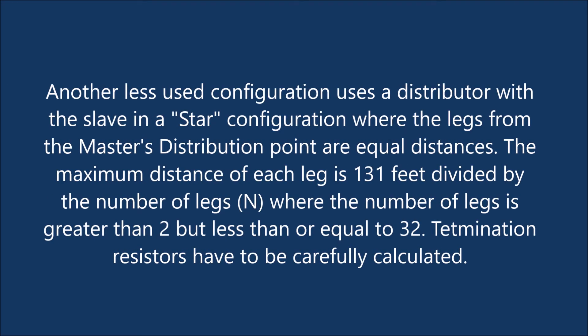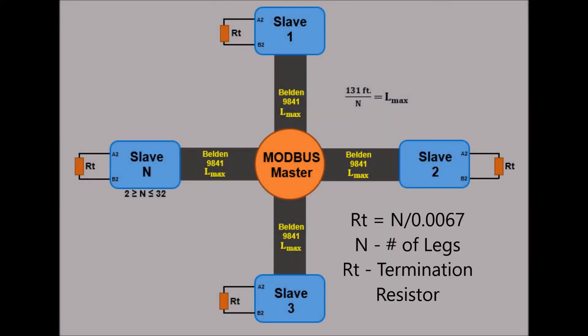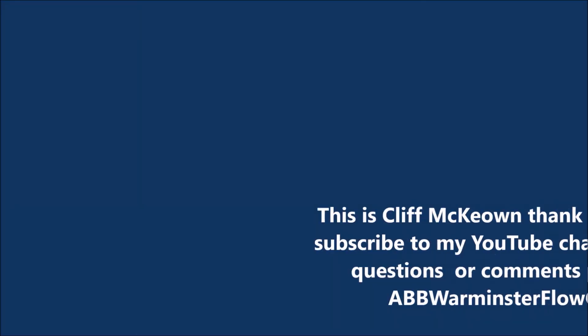Another less-used configuration uses a distributor with the slave in a star configuration, where the legs from the master's distribution point are equal distances. The maximum distance of each leg is 131 feet divided by the number of legs N, where N is greater than 2 but less than or equal to 32. Termination resistors must be carefully calculated: Rt equals N divided by 0.0067, where N is the number of legs and Rt is the value of the termination resistor.